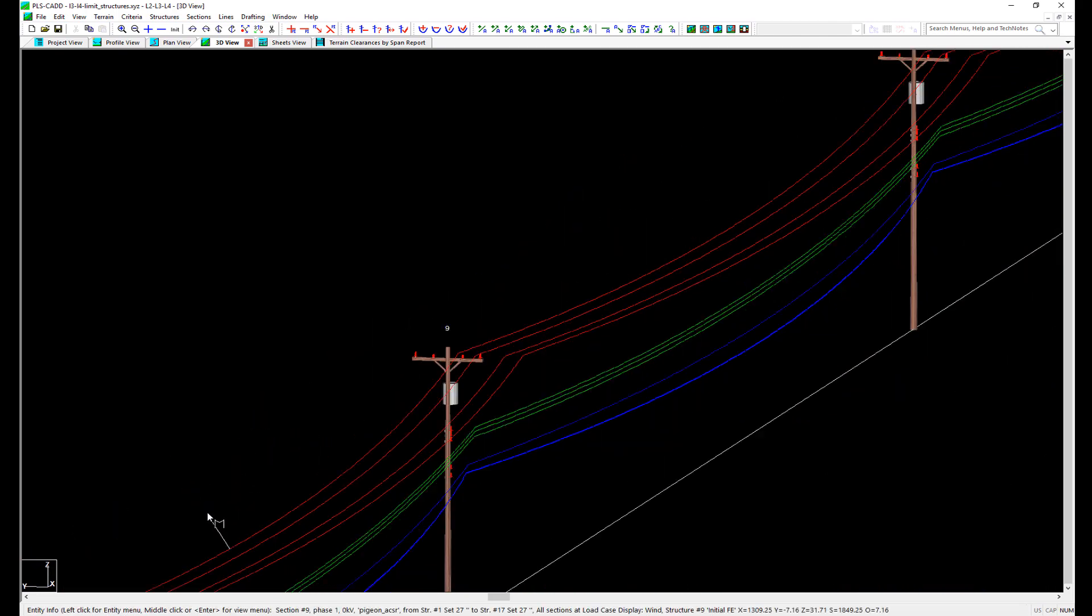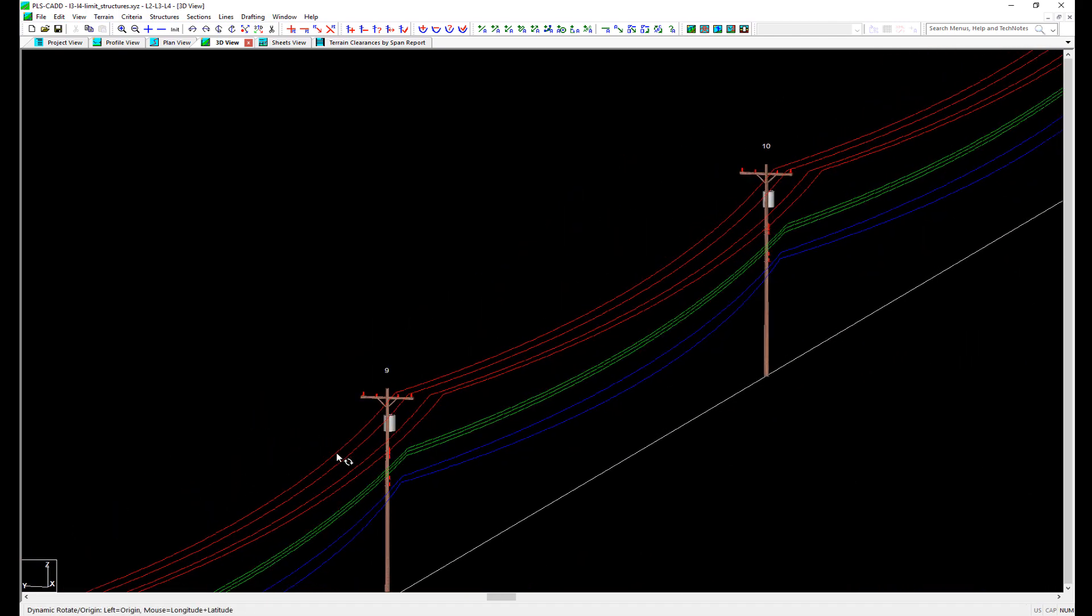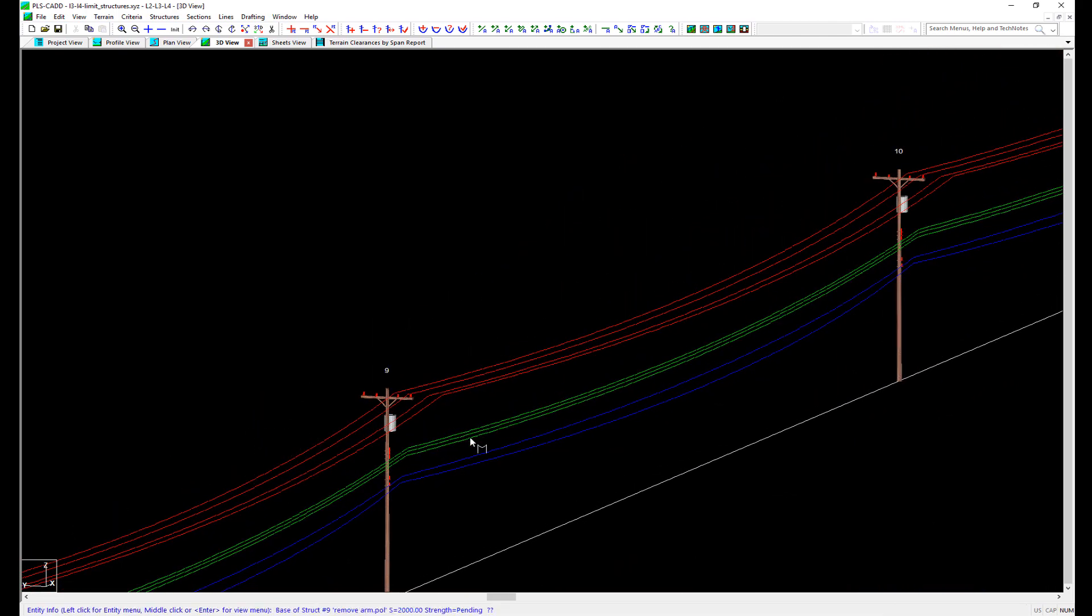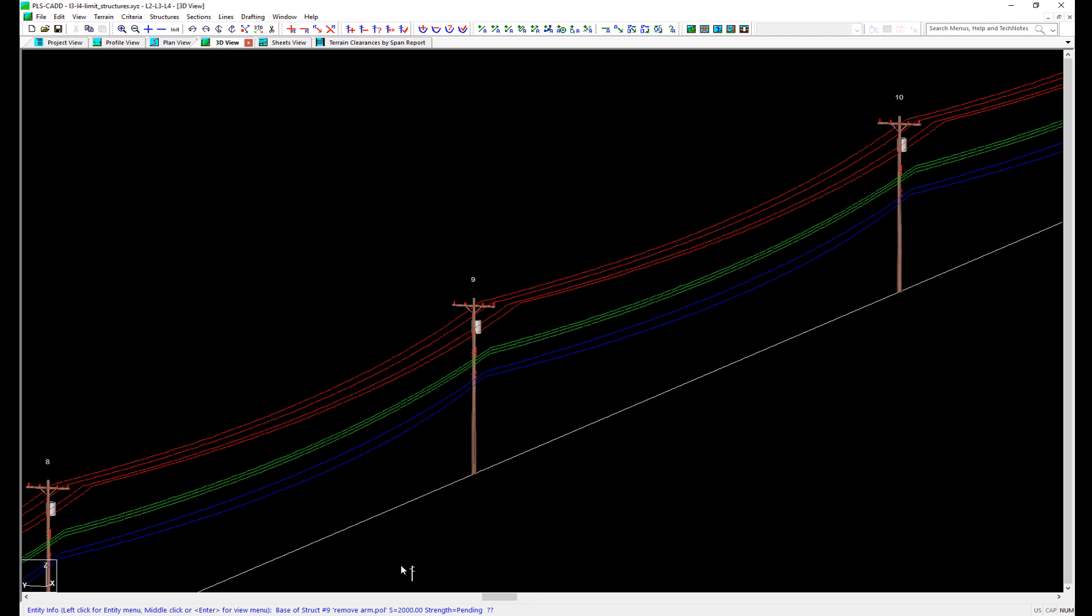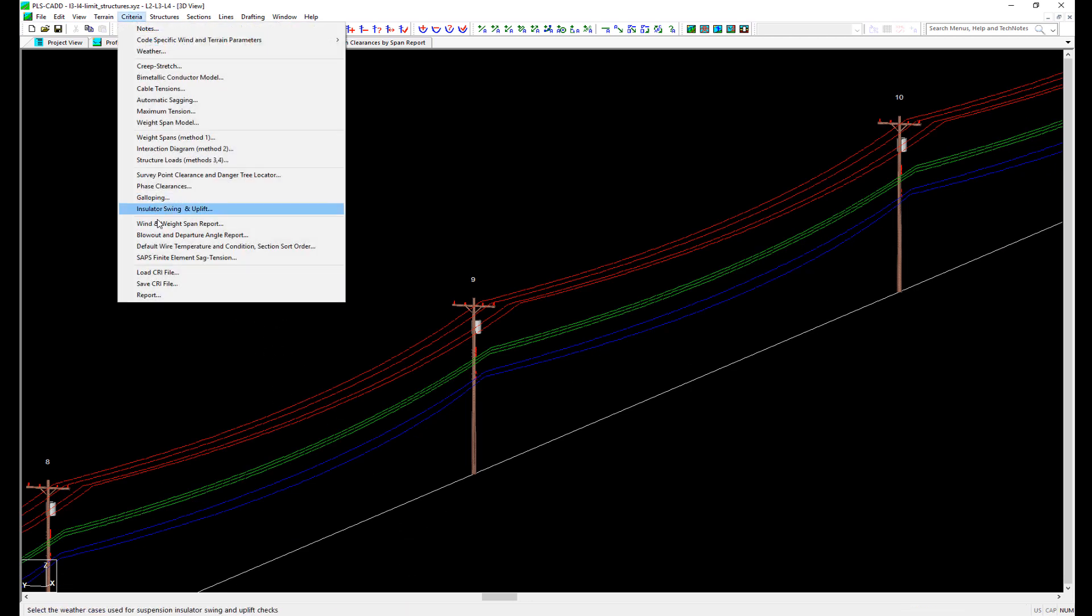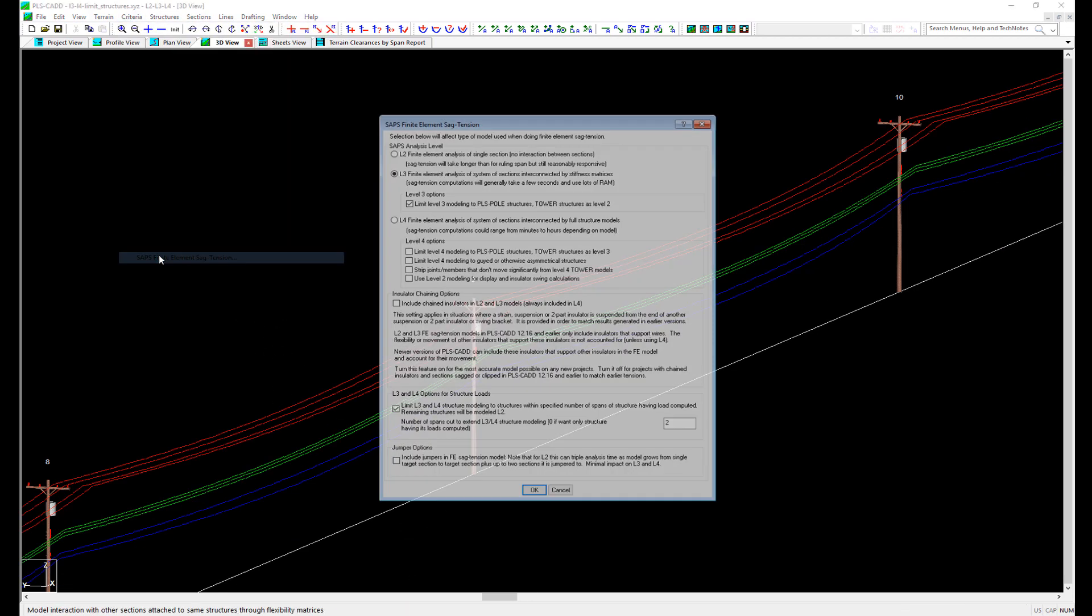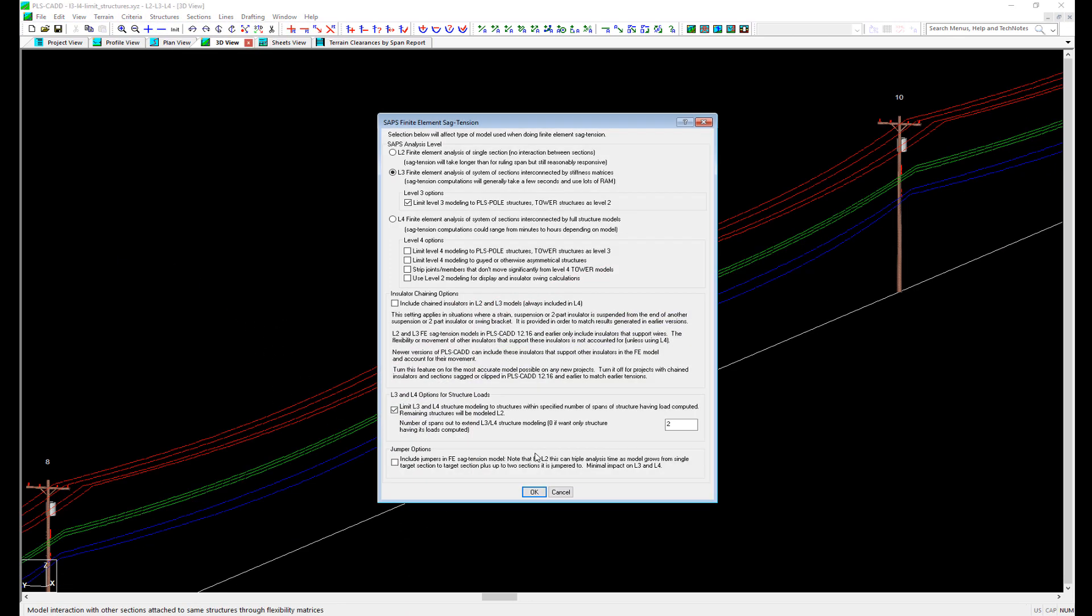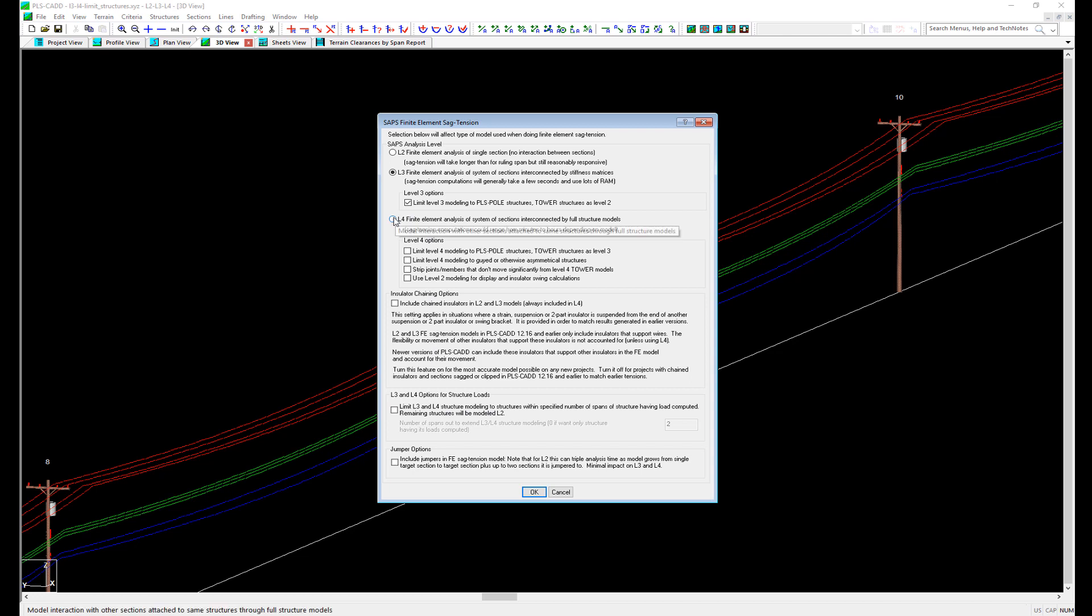It will depend on your project, but in general, two flexible structures beyond the one being checked will give results similar to a full L3 or L4 analysis. Going back to the SAPS criteria again, we can enable the option for SAPS level L4. An L4 analysis is the highest level of analysis and uses full structure models in the sag tension analysis to calculate deflections. Because of this, it can take a bit longer to analyze compared to L3.